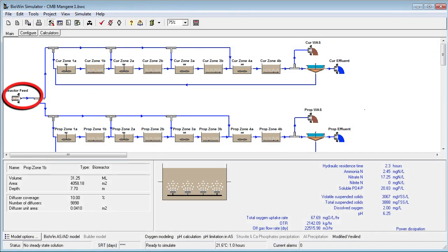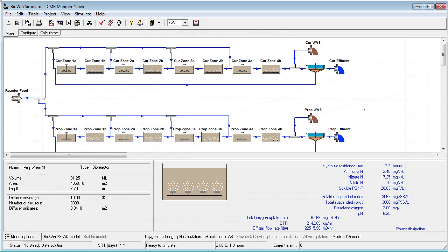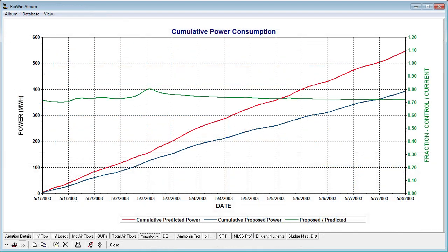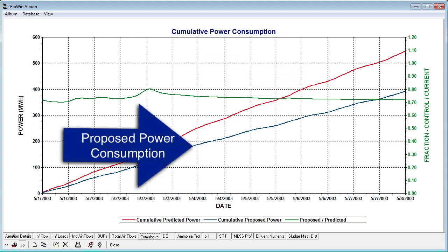An average week plant load was represented as a dynamic time-varying influent. This load was directed to a model representation of the current mode of operation and the proposed mode of operation. The plant's relationship between air flow and power consumption was input to the model, and the predicted power consumption for the current control strategy, shown by the red line, was compared to the predicted power consumption for the proposed control strategy, shown by the blue line.